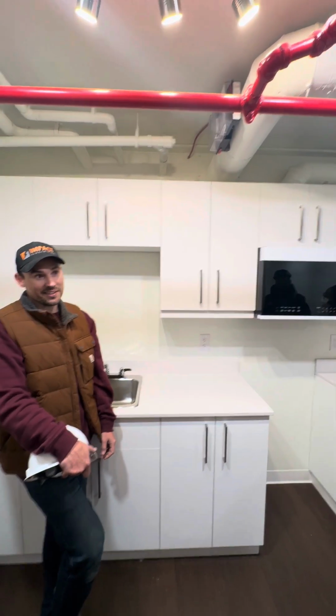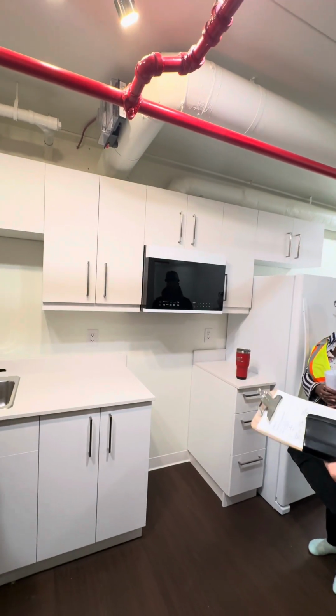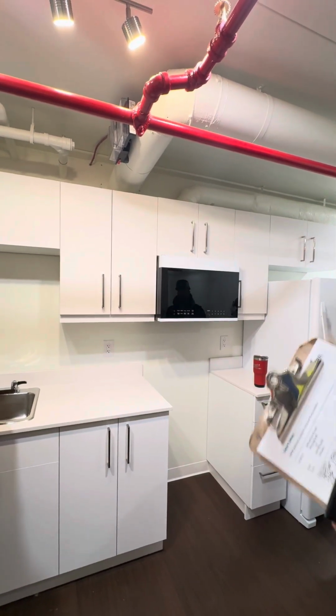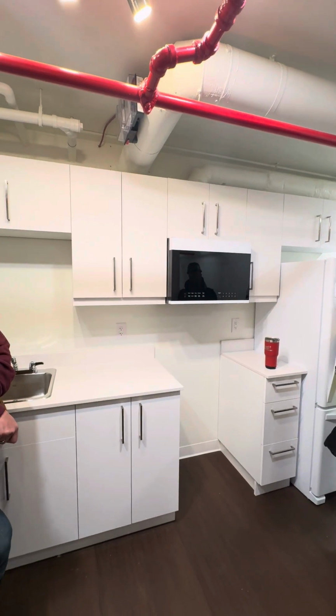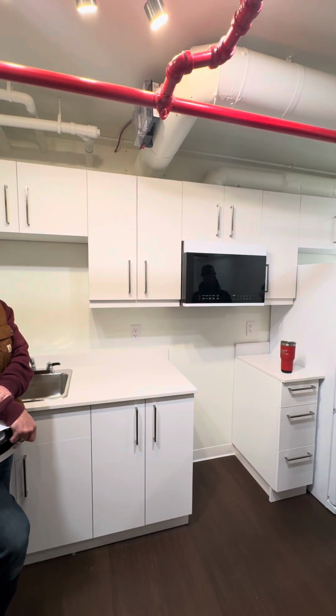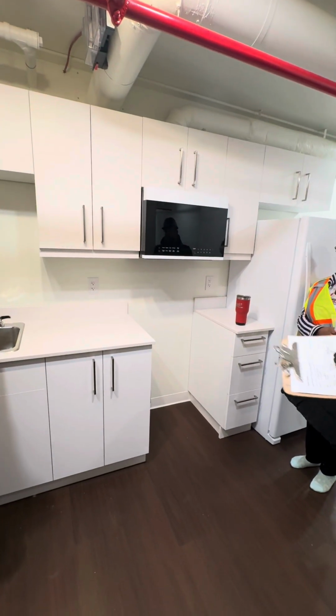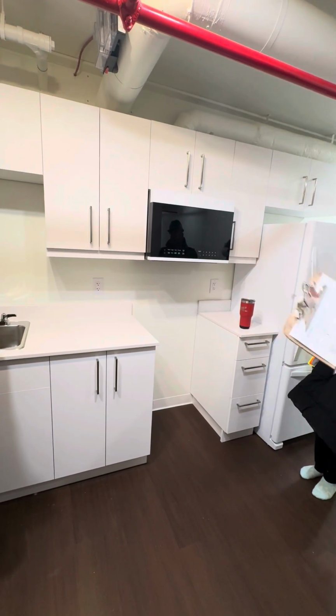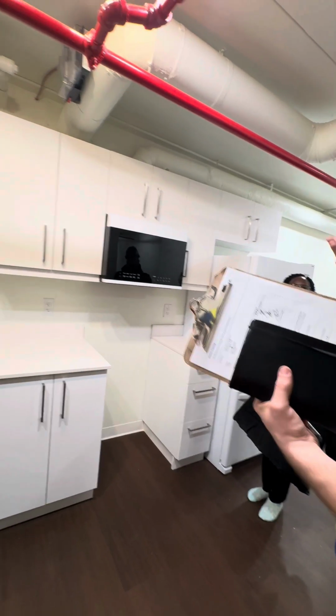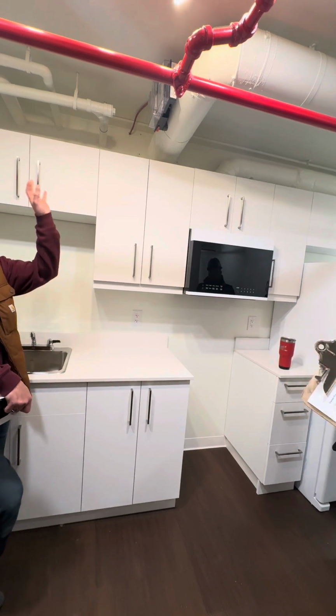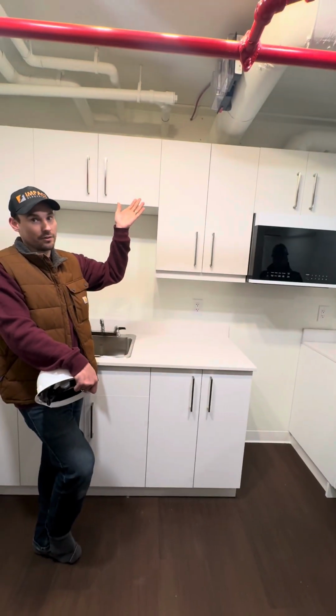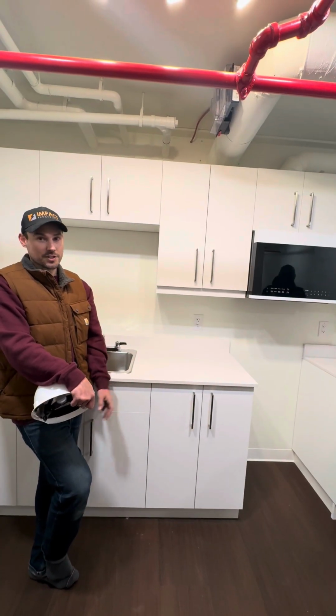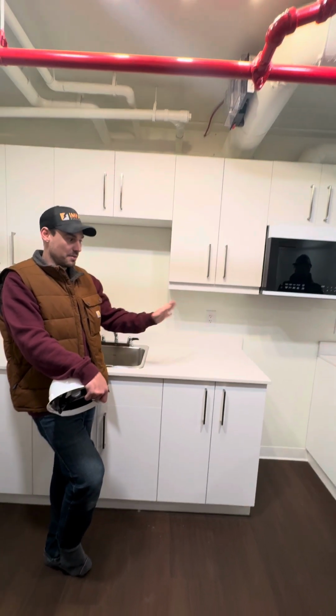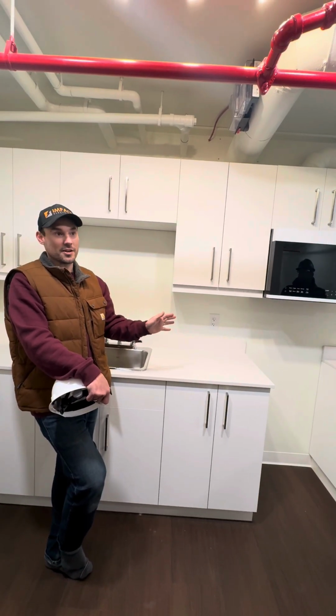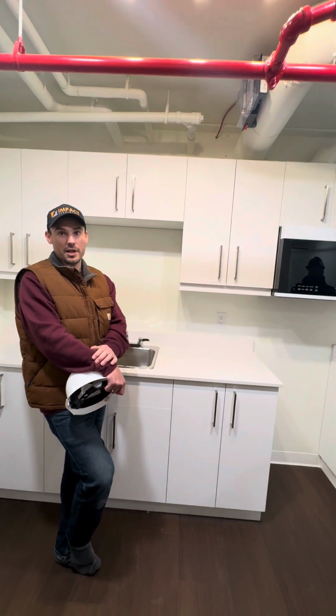The reason I wanted to bring this one up specifically is that we were talking with the engineers about this smoke damper because of its proximity to an oven. We tried to ask if there was somewhere else we could put it, but they said it needs to go here. So if someone is cooking and something smelly burns and creates smoke, it could cause an alarm. It is a sealed unit, but smoke can travel through a pinhole, so there is a possibility this could cause nuisance alarms in the future. The engineer made us install it in this area, so if it's nuisance tripping down the road, that's something you guys can look into on your own.